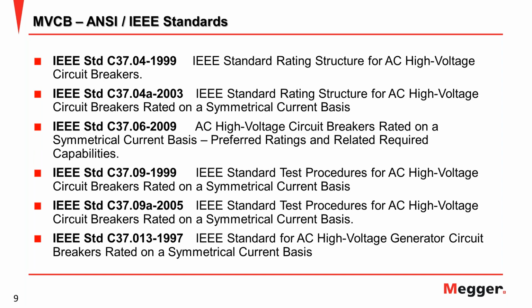Okay, now we move to some standards to be used for circuit breaker tests. The famous standard is IEEE C37.04-1999. This is the IEEE standard rating structure for AC high voltage circuit breakers. In this standard, you can see some testing procedures and some criteria to define whether the breaker is in good condition or needs investigation based on certain testing.